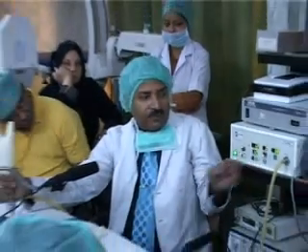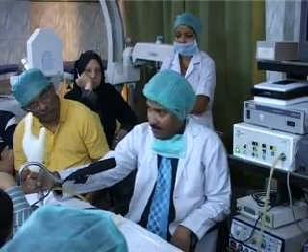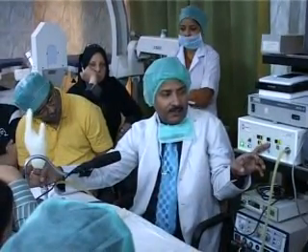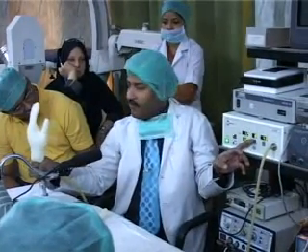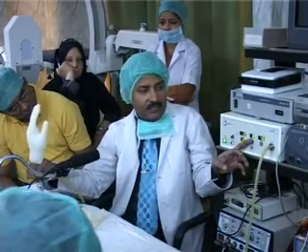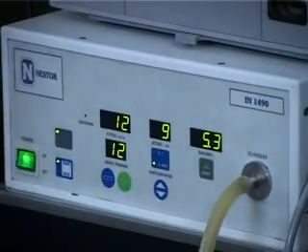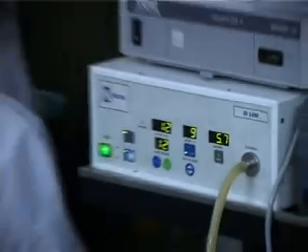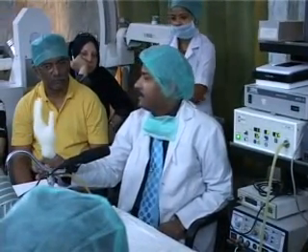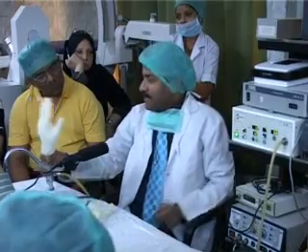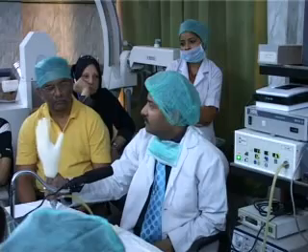Right now the flow rate is 0, but now I am leaking. I am leaking now, and the flow rate is 1 liter per minute. Now I am leaking further. Flow rate is 5 liter. Now the flow rate is 8 liter. Now the flow rate is 10 liter, and still the distension of the abdomen is maintained. Can you see? It's a big leak. I have almost stopped it, and it's a big leak, and it is compensating. But if I stop it, it will gradually go down and come to 0.